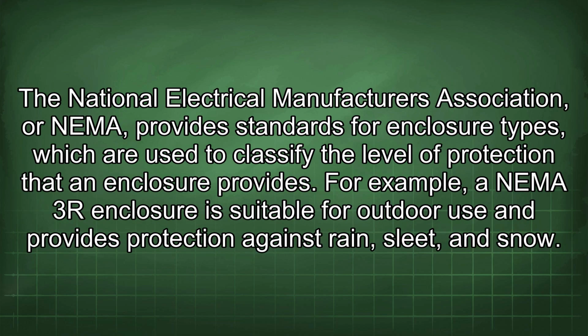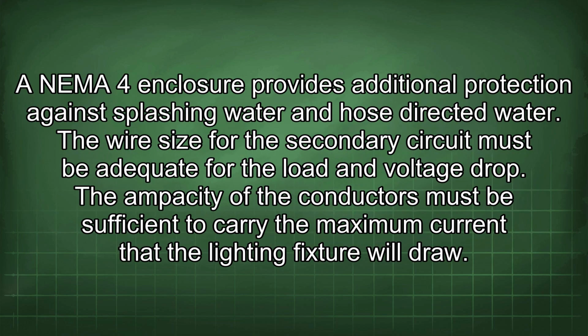The National Electrical Manufacturers Association, or NEMA, provides standards for enclosure types, which are used to classify the level of protection that an enclosure provides. For example, a NEMA 3R enclosure is suitable for outdoor use and provides protection against rain, sleet, and snow. A NEMA 4 enclosure provides additional protection against splashing water and hose-directed water.